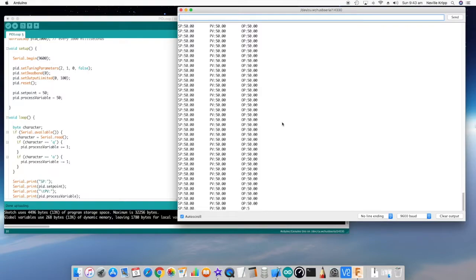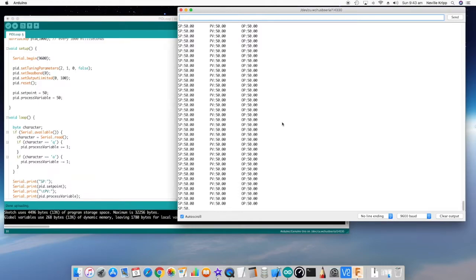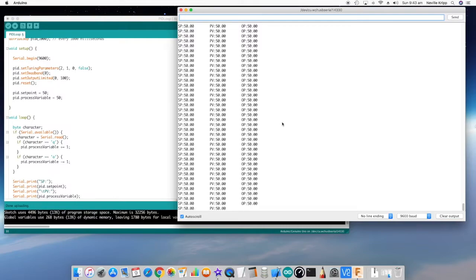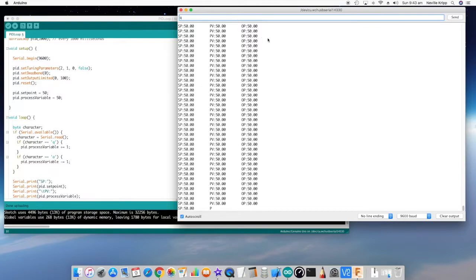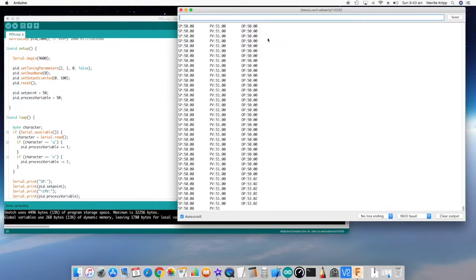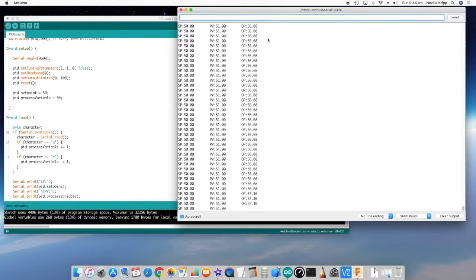Everything's in a steady state condition—50 set point, PV of 50, so there's zero error and the output is just sitting nicely on that 50. Now the way the integral term works is it will tend to keep varying the output when there is an error, trying to bring the loop back into control. So it integrates any error in the actual control loop. As an example, if we send a Q, it will give us an error of 1 and we should see a proportional action of 2 be applied straight away, so it goes up to 52, but you'll notice that it's keeping on going up.